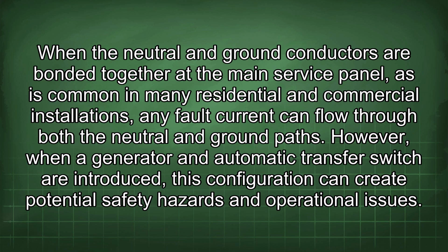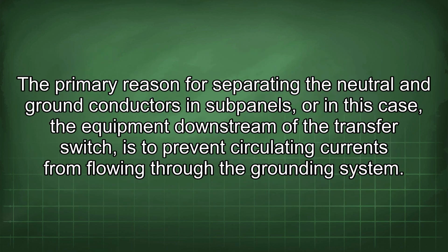When the neutral and ground conductors are bonded together at the main service panel, as is common in many residential and commercial installations, any fault current can flow through both the neutral and ground paths. However, when a generator and automatic transfer switch are introduced, this configuration can create potential safety hazards and operational issues. The primary reason for separating the neutral and ground conductors in subpanels, or in this case the equipment downstream of the transfer switch, is to prevent circulating currents from flowing through the grounding system.